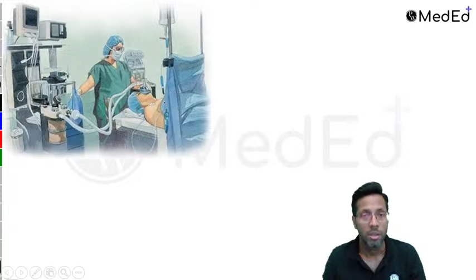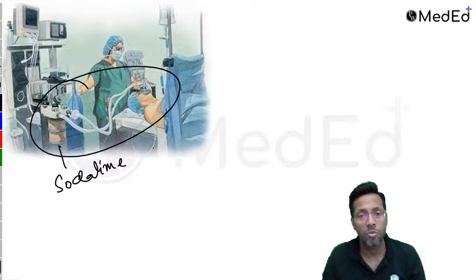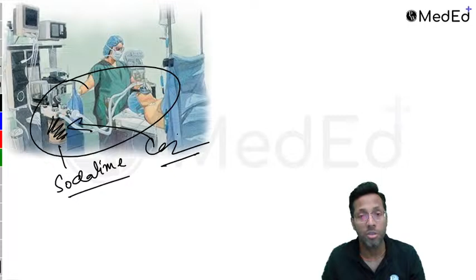Absolutely. This is what is called closed circuit. Closed circuit is where you're using soda lime. Soda lime is something which absorbs carbon dioxide. Okay? Soda lime absorbs carbon dioxide. Therefore, soda lime has a capacity to absorb carbon dioxide, and after some time this will get exhausted, right? How will you come to know that it is exhausted? You will come to know from the clinical signs, right? Increase in carbon dioxide, and you will come to know from the color change.